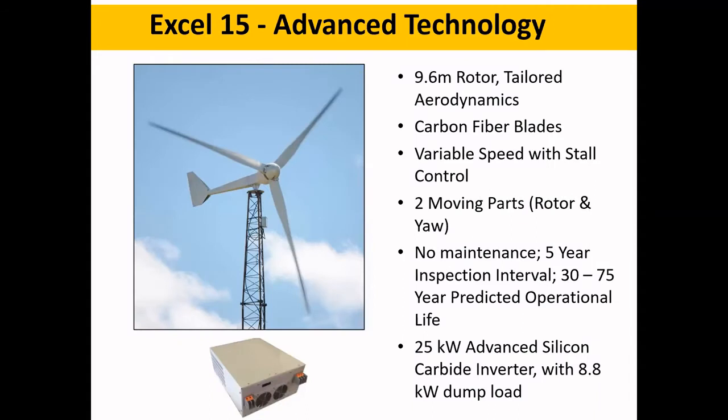The new turbine is 9.6 meters in diameter with tailored aerodynamics — that's the secret sauce, the same recipe large turbine manufacturers use but requiring a lot of R&D work. The blades are carbon fiber and glass composites, requiring new affordable manufacturing methods. It's a variable speed machine with stall control, doesn't furl, has only two moving parts, and is designed for no scheduled maintenance — just a five-year inspection interval. Based on our older designs running 35 years, we're projecting a 30 to 75 year operating life, matched with an advanced silicon carbide high-frequency switching inverter and an 8.8 kilowatt dump load.